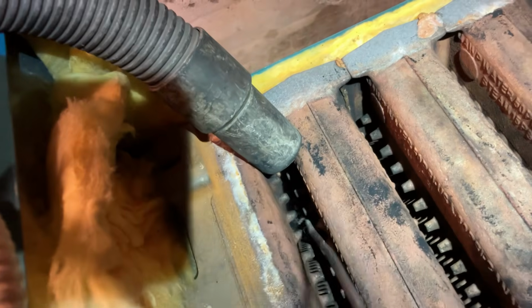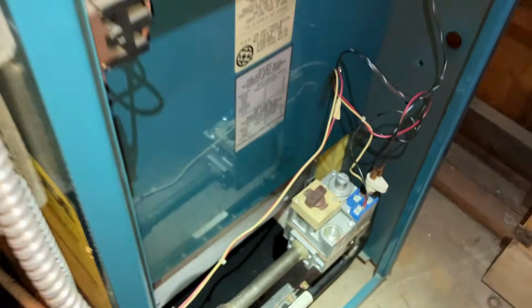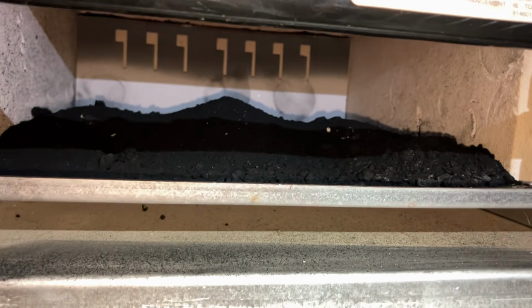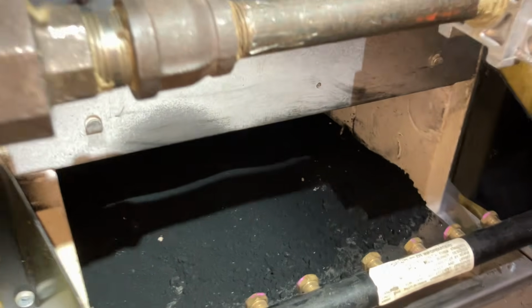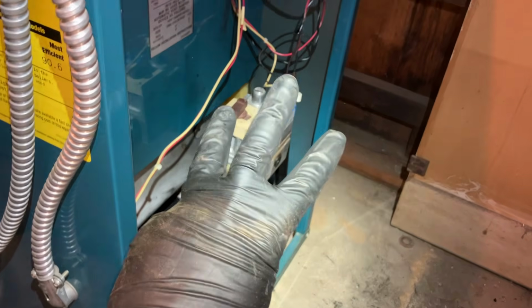I'm at the last passageway between the sections, and you notice I went from the front of the boiler on an angle and also from the back of the boiler on an angle closer to the front. So it's hard to see in there. Let's see if I can show you. Significantly clean, but what's shocking is going to be mind-blowing for you. That is mountainous. That is mountainous. And that's just one of 3 passes.